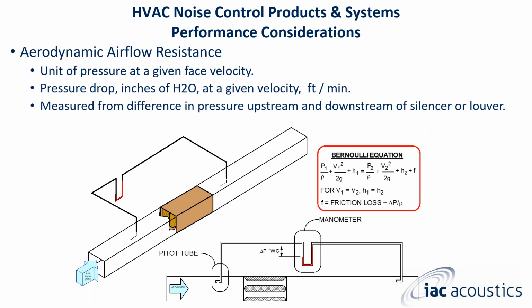We are getting ready to go through a whole round robin of testing where you are going to see online and in video how a pitot tube is installed on either side of the silencer, air flowing into the ductwork through the silencer, through both areas of the pitot tube, and how this is actually measured in the manometer. It is measured with water inside that area where you see red. The difference then is the actual pressure drop.